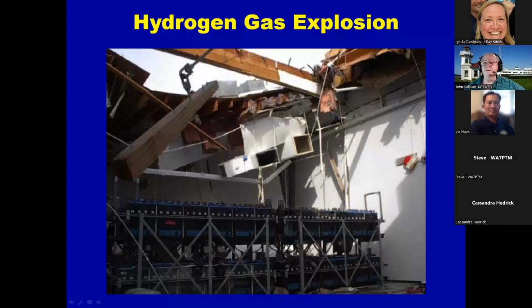Eventually there was some ignition source, probably at a grounding strap or who knows what, but something provided the spark that set off a hydrogen gas explosion. The lesson here is that ventilation is critical with lead acid batteries. You really have to make sure the ventilation is adequate, and you never want to be charging the batteries if it's not well ventilated. So that's what that picture is all about.